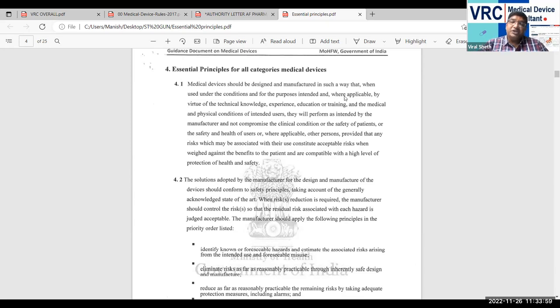Now they want some surety from the medical device manufacturer or importer - at least you should ensure patient safety when you put that device on the market. So here we have to confirm there is a specific standard for that to ensure the risk analysis. The risk analysis of the device is conducted to understand what the minimum risks associated with our device are. So to conduct the risk analysis, we should follow ISO 14971.